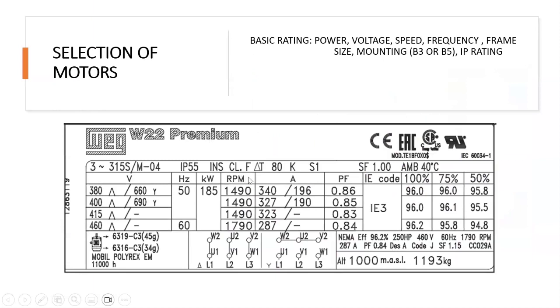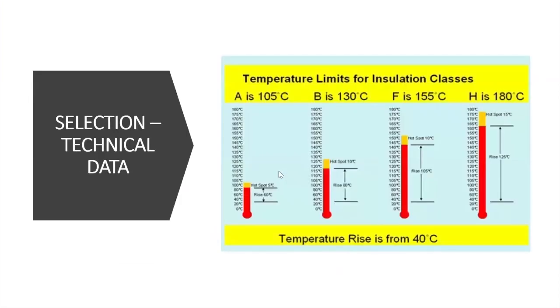On the nameplate data of this one, the insulation class is F, which means the motor can go up to 155 degrees Celsius. But it is stated on the nameplate that the temperature rise is 80 degrees Celsius. So though it has an insulation class of F, but it has a temperature rise of 80 degrees Celsius. So if you install it at an ambient temperature of 40 degrees, you do not expect the motor to fail at 155. It will fail when the temperature rise up to 80 degrees. So let's say 120. But advantage is that at a hotter ambient temperature, like an ambient temperature of 70, you can still use this motor, because at a temperature rise of 80, you'll be around 150, which is near to the breakdown temperature, which is 155.